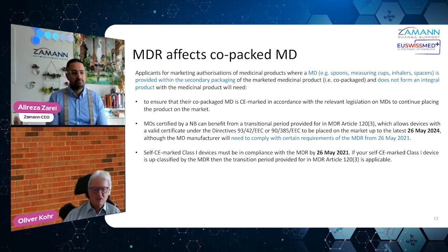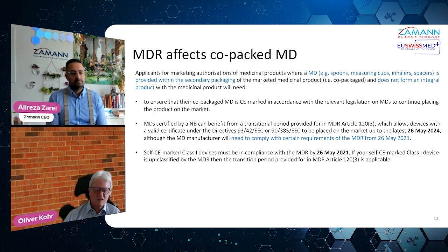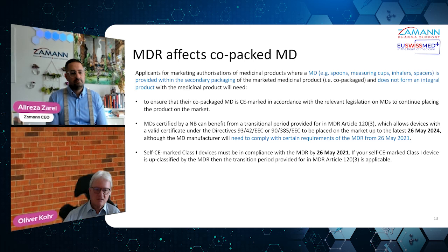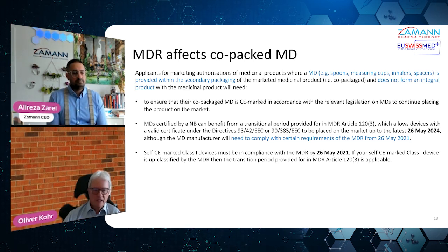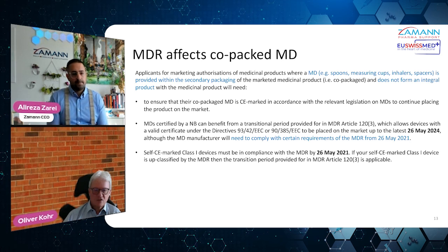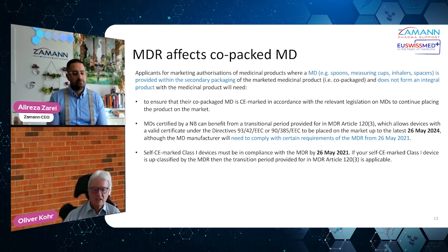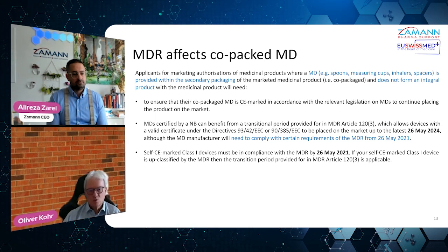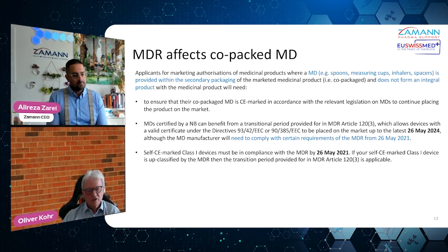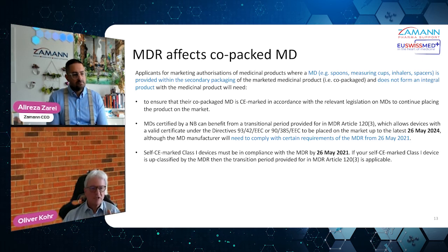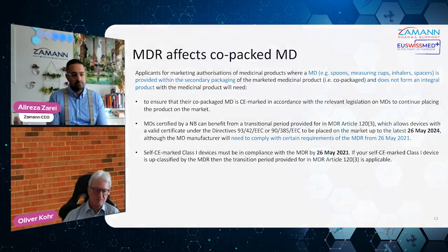Self-marked CE devices must be in compliance right away, because class 1 has no transitional phase as such for medical devices. So you need to be compliant already as of today with class 1, because it's self-certified. You issue yourself the declaration of conformity, it's all yourself. However, your notified body who audits you may then look into the documentation, the declaration of conformity, and all these kind of things where you stick to the process.